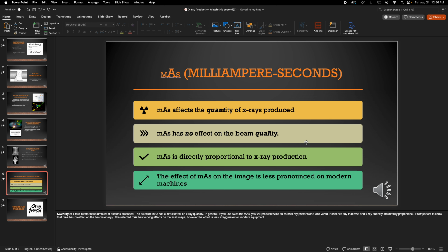mAs, you've got to know how to change that too. However, here's the difference. Whereas in X-ray you make mAs selections, as in how much current and for how long, in CT you change mA, because how long depends on the pitch, or how fast the table is moving, right? How long you're exposing the patient for. So you don't use mAs, so to speak. You select mA, and then the dose is calculated by DLP, as I would call it, DLP, or dose length product.